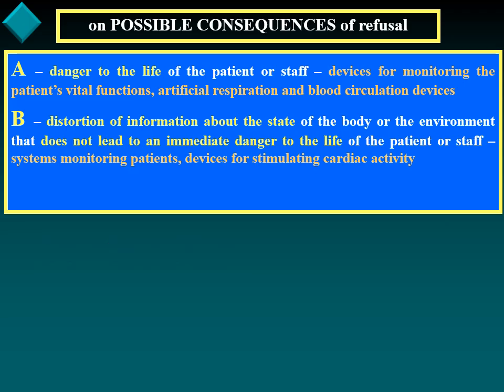Depending on the possible consequences of failure during operation, medical devices are divided into just 4 classes. The first class is Class A. Here are products whose failure poses an immediate danger to the life of the patient or staff. The probability of trouble-free operation of a product of this class should be at least 0.99. Products of this class include devices for monitoring the vital functions of the patient, artificial respiration devices, blood circulation.